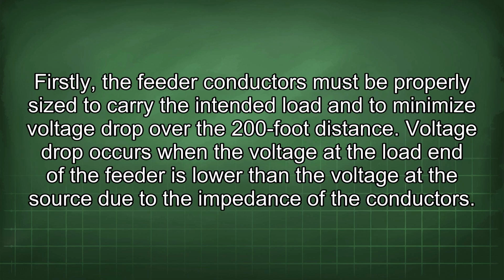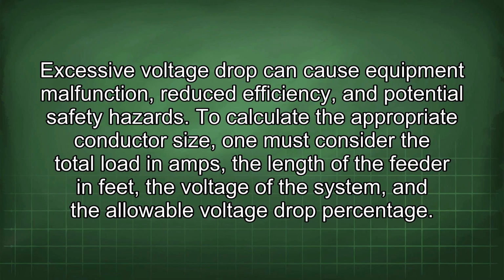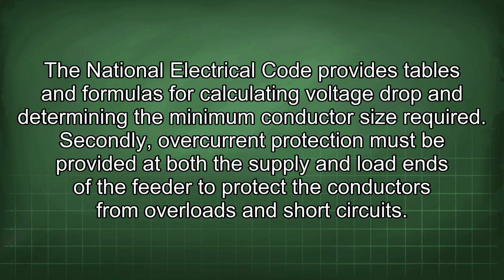Firstly, the feeder conductors must be properly sized to carry the intended load and to minimize voltage drop over the 200-foot distance. Voltage drop occurs when the voltage at the load end of the feeder is lower than the voltage of the source due to the impedance of the conductors. Excessive voltage drop can cause equipment malfunction, reduced efficiency, and potential safety hazards. To calculate the appropriate conductor size, one must consider the total load in amps, the length of the feeder in feet, the voltage of the system, and the allowable voltage drop percentage. The National Electrical Code provides tables and formulas for calculating voltage drop and determining the minimum conductor size required.